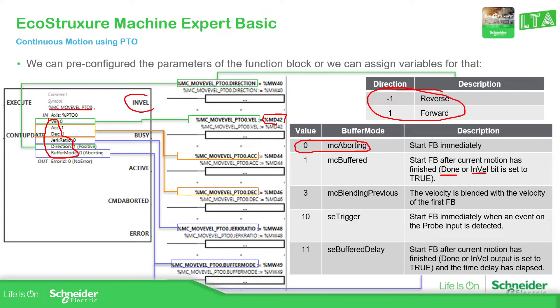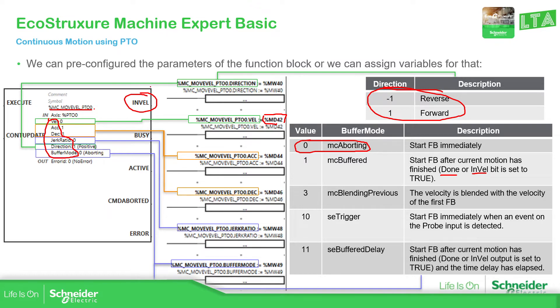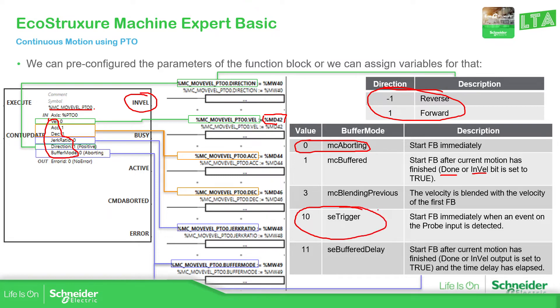And this one, the buffer, depending on the previous movement, it will start after the other one is finished. You can see that you have the done or in velocity. For example, if I have two move velocity, it will start until this one is in velocity. We don't have done because we just assign, it goes to the velocity and then just go to that velocity. And then we have Blended, Trigger and Set Buffer. This one, we're going to see it later regarding to the touch probe that we have. So we're going to cover that later.